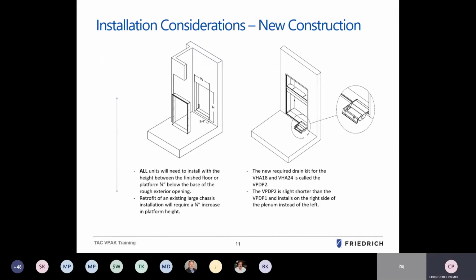Some installation considerations with regard to new construction. All the units will need to install within the height between the finished floor and the platform, 3/4 of an inch below the base of the rough exterior opening. That's a critical measurement to remember because you don't want to install it too high or too low, so that the unit doesn't slide into the plenum, and making sure that the unit fits comfortably against the rubber gasket without tearing it or kinking it or pinching it or damaging it altogether.